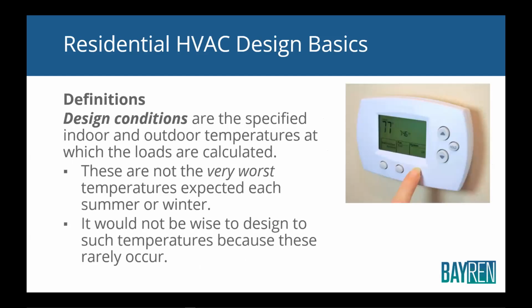So design conditions are the specific indoor and outdoor temperatures at which the loads are calculated. These are not the very worst temperatures expected. These are specified by code. For cooling, it's what's called the one percentile. And for heating, it's this winter median of extremes number. And again, don't let contractors arbitrarily increase the design conditions because they say, oh, it's gotten really hot lately. You have to realize that when they say, oh, that was a 100-degree day, we've had a lot of 100-degree days over the summer, and your design temperature might be 95. Well, there might be a lot of days where it hit 100 degrees, but if you look at the actual temperature on that day, it was only 100 degrees for a very, very short period of time. So there's no need to design it to 100 degrees.